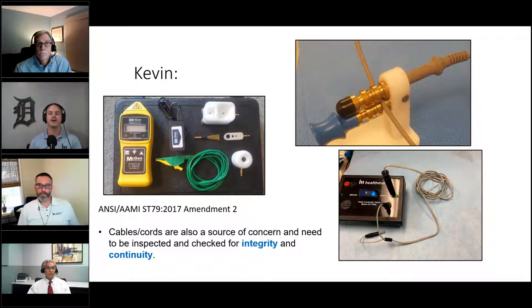On the lower right you have the continuity tester, which helps ensure the electrical wiring inside the insulation is also intact. These cords are often reusable, and many don't even have an end-of-life requirement in the IFUs—some do, but many don't. There's a possibility the insulation could be great, but the metal wiring can be broken from wear and tear. When this happens, the electrical current may have to arc to get where it's going, and we don't want that inside the cord, because it can cause burning of the insulation and potentially a spark and severing of the cautery cord while in use.